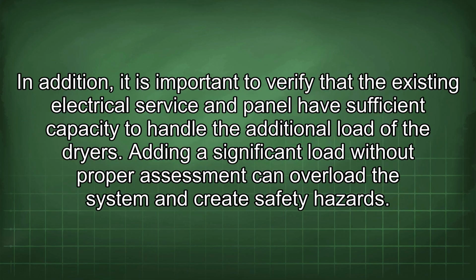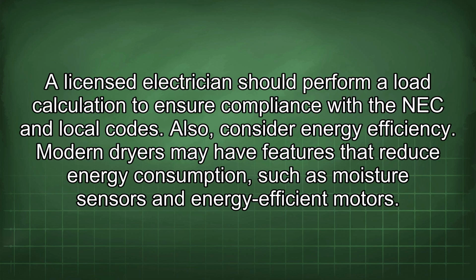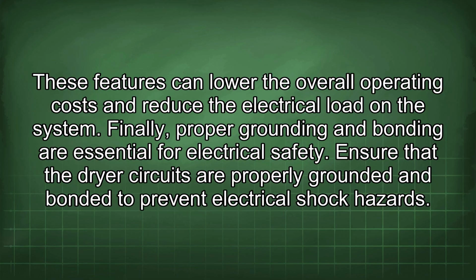In addition, it is important to verify that the existing electrical service and panel have sufficient capacity to handle the additional load of the dryers. Adding a significant load without proper assessment can overload the system and create safety hazards. A licensed electrician should perform a load calculation to ensure compliance with the NEC and local codes. Also consider energy efficiency. Modern dryers may have features that reduce energy consumption, such as moisture sensors and energy-efficient motors. These features can lower the overall operating costs and reduce the electrical load on the system.